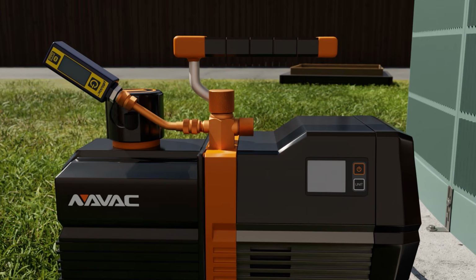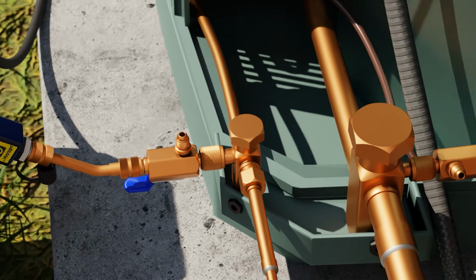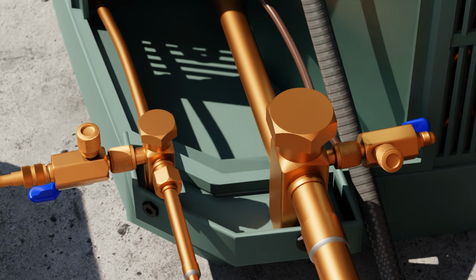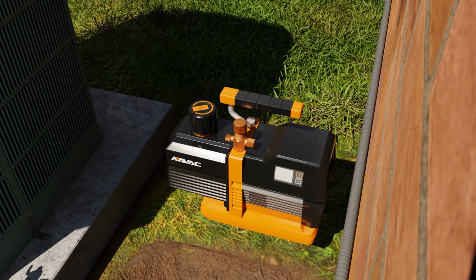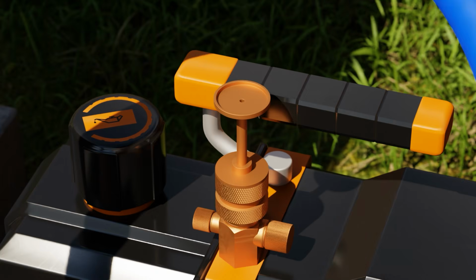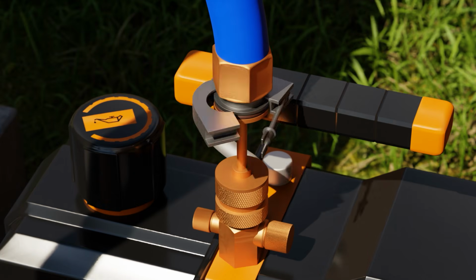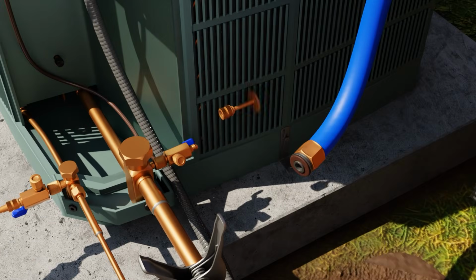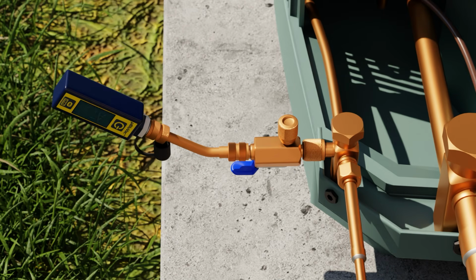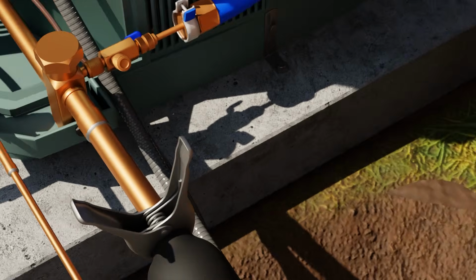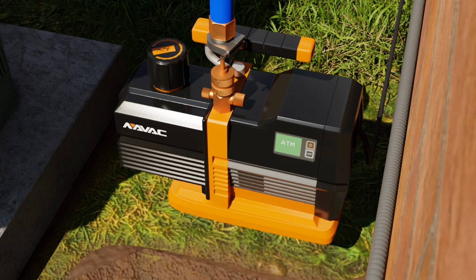Now, connect your micron gauge to the liquid line valve. In this case, both of our Schraders are still out of the suction and liquid line. Here we're showing the True Blue vacuum hose, which is one of the highest capacity vacuum hoses available on the market today and the ones that we use primarily at Kalos. Now turn on your vacuum pump and let the system pull down.